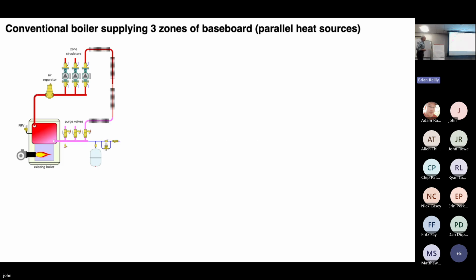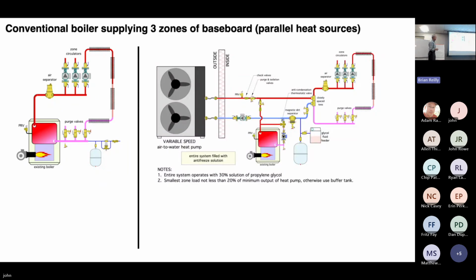Now, since we've got time, I'll run through these system examples. All right, let's start with this. This is very common: you've got a conventional boiler, let's say a cast iron, oil-fired boiler, and we've got three zone pumps on it and some fin tube. So we want to add an air-to-water heat pump to that. Here's one way we could do that. If you study this back and forth, I've tried to preserve as much of this as I can. In other words, I don't want to take that whole header apart and reposition all those circulators if I don't have to.